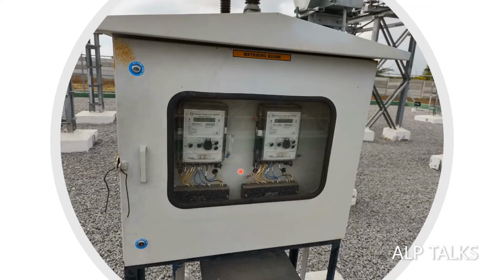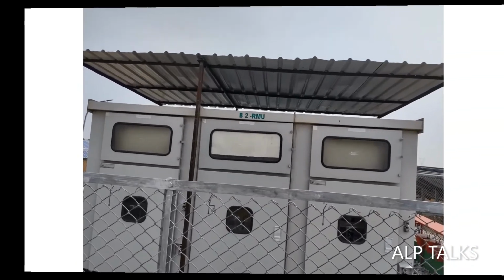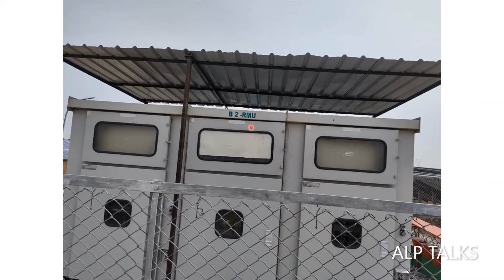So this is the meter arrangement. It will record the energy units generated from the plant and how much is exported to the government network. That is what it will show here. We have 2 meters. I think one can be maximum load and another can be total units generated. So this is a ring main unit. Whatever power is generated from the individual inverter duty transformers, all of it will come to one particular place and then is routed to the power transformer. This is the ring main unit.